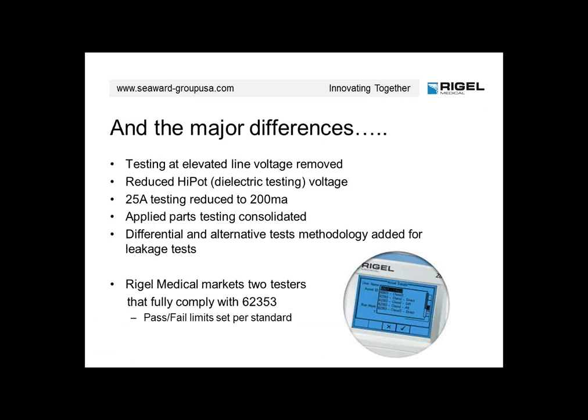So what are the big differences between 60601 and 62353? Testing at elevated line voltage is removed. One of the specifications for 601 was that a test had to be conducted at plus 10% of the line voltage. 353 does away with that. High pot or dielectric testing is reduced. And frankly, probably none of you did this in the field anyway. This was always done at the manufacturing site, and the unit is tested at 3 or 4 kilovolts, perhaps up to 5 kilovolts, to see if there's any dielectric leakage.